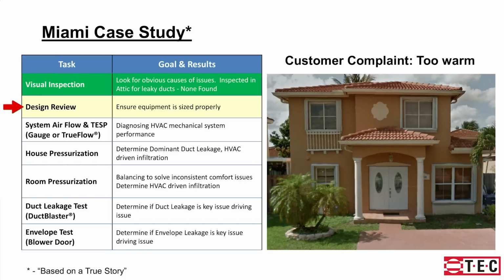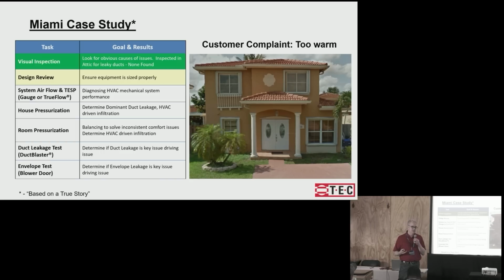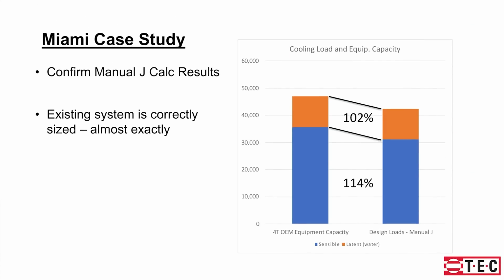Okay, so if a system's not keeping up, is it big enough for the house? Only way to know that is to do a load calc. Maybe you can look at runtime, but if it's not keeping up, it's going to be 100%. So load calc is a next step. And in this case, the technician did the load calc.